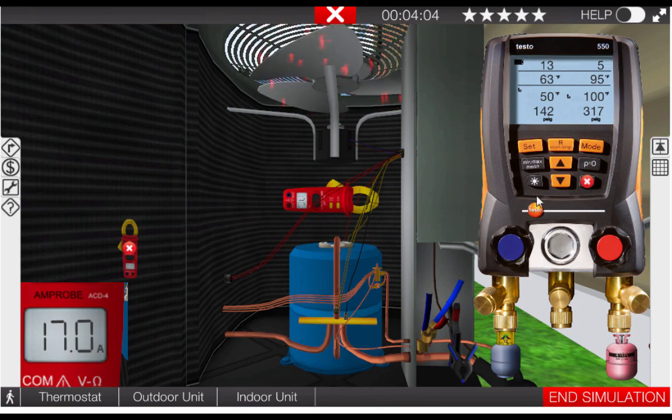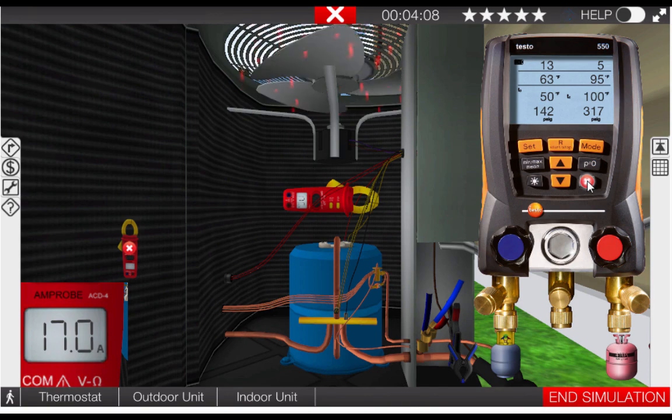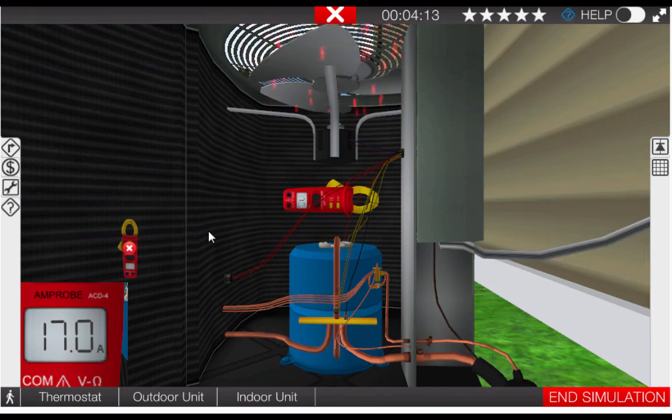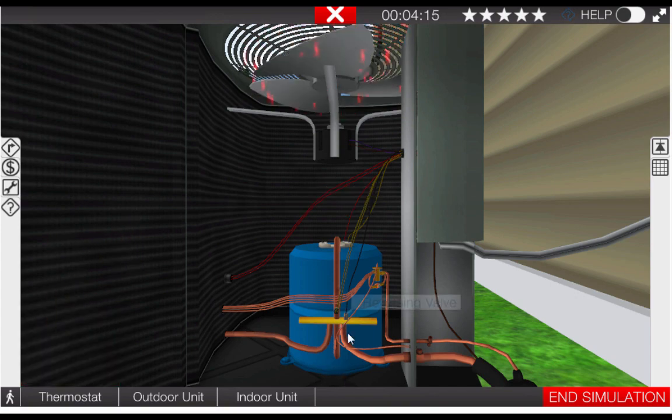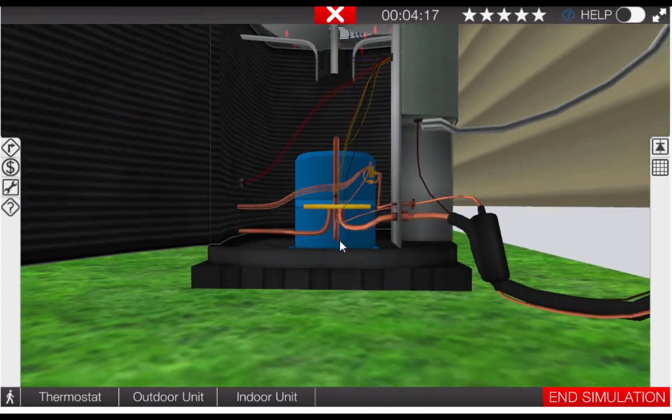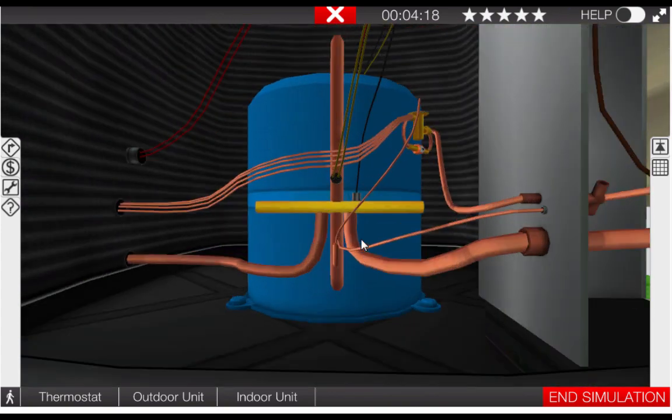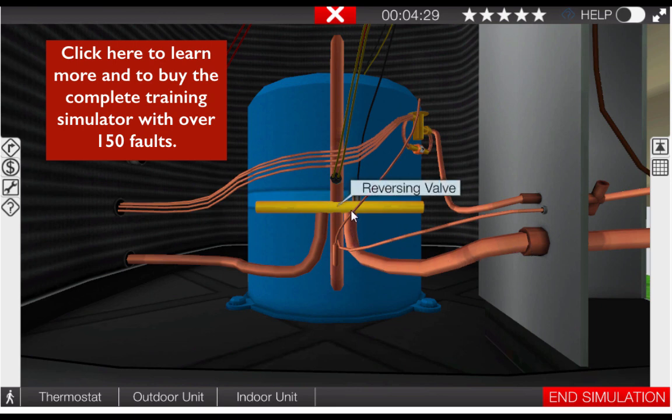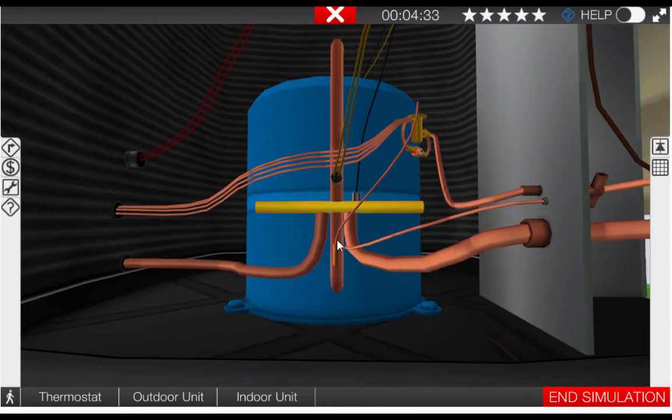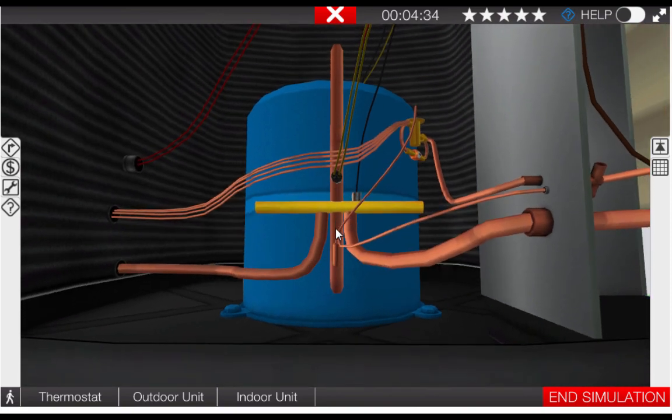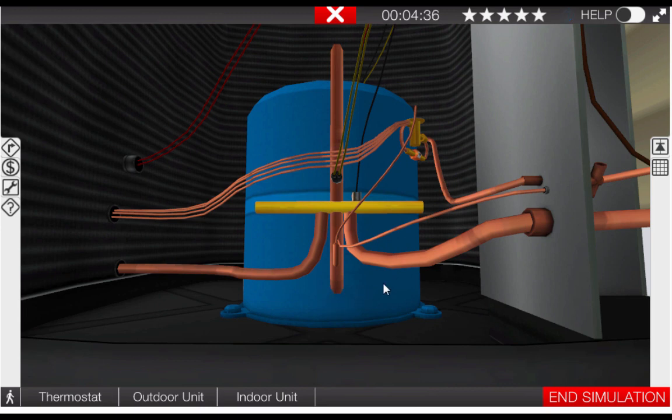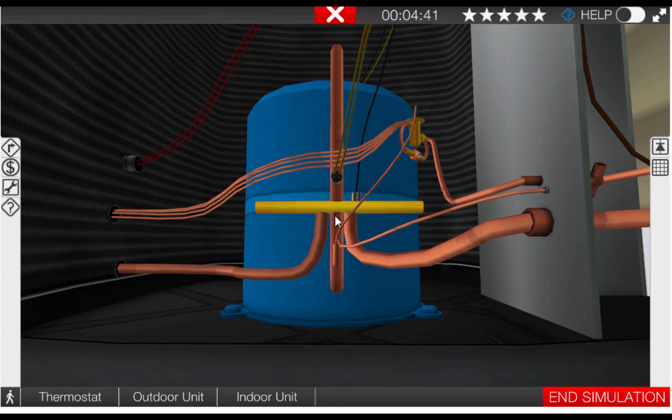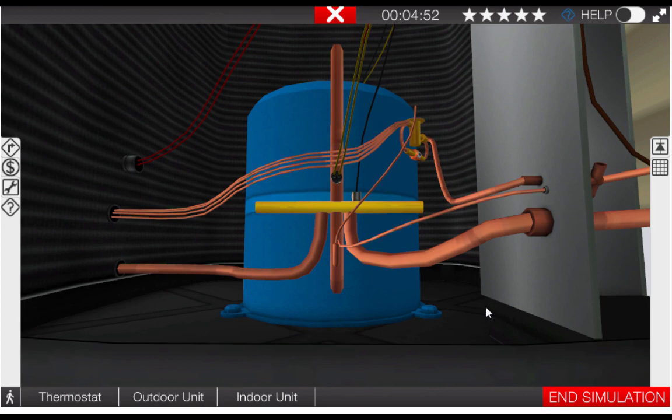I'm going to store these instruments back in the toolbox and show you another way of verifying an internal leak on the four-way reversing valve of the heat pump. Looking at the reversing valve if you were to measure the temperature of the two suction ports of the reversing valve. In other words this line right here is where the suction gases are entering the valve and the center line at the bottom is referred to as the permanent suction port which is going back to the compressor. We should not have any more than a three degree increase in temperature as this suction gas passes through the body of the valve. Any measured temperature difference across the two suction ports in excess of three degrees Fahrenheit will just simply verify the internal leak.